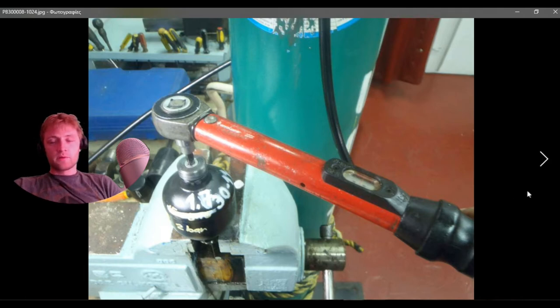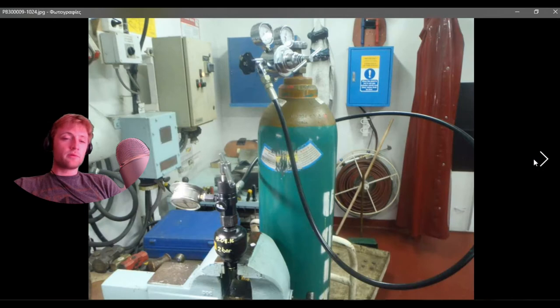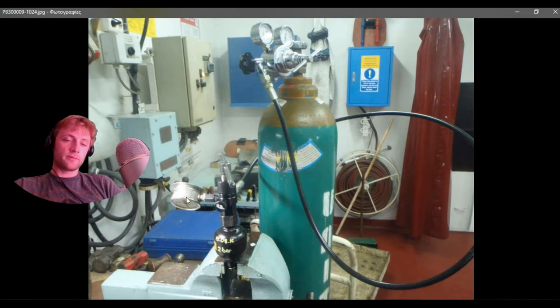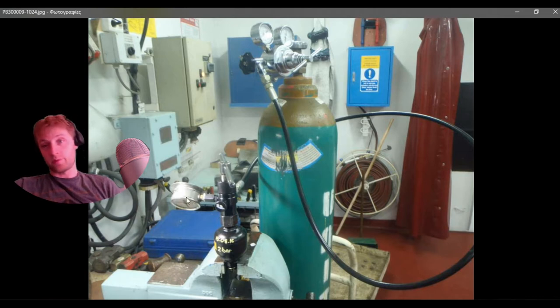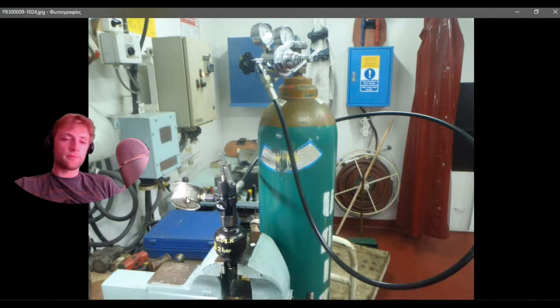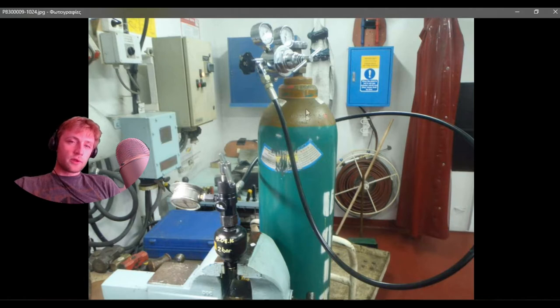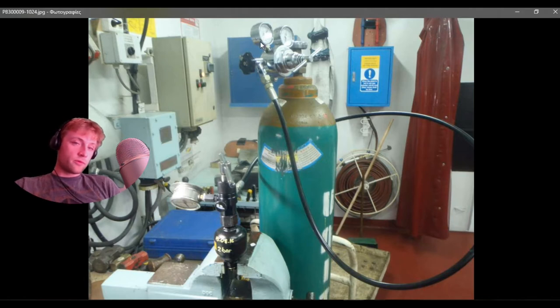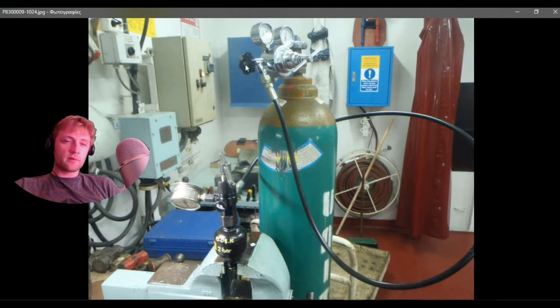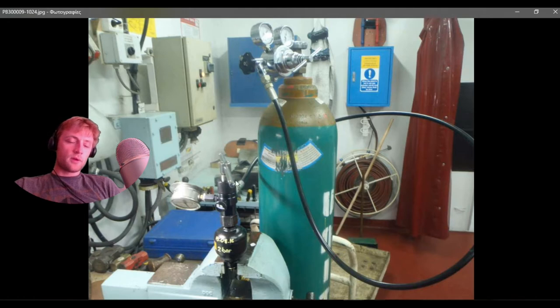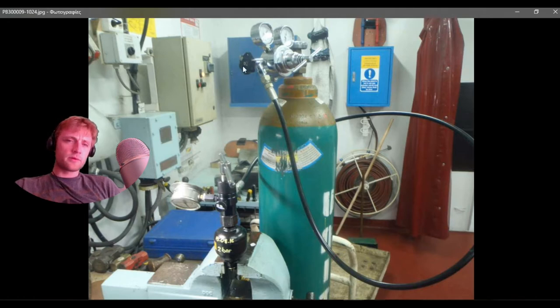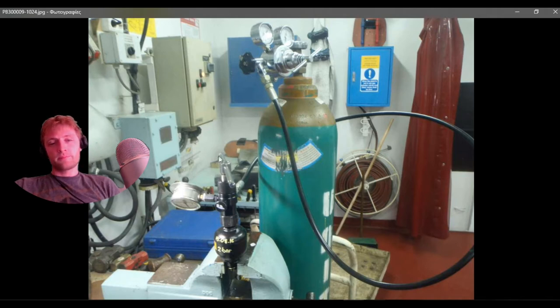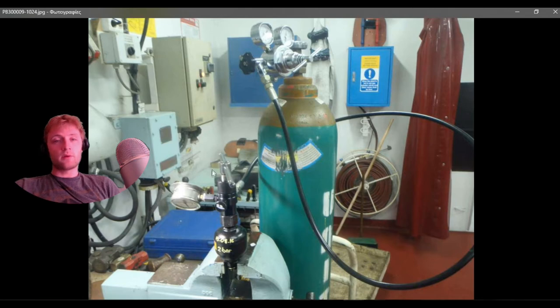What is going on when you like to fill the accumulator? As you can see, we have a dial pressure gauge here. What you do is regulate the pressure which you will fill, about two bars, and slowly open this black valve. You can open it full.